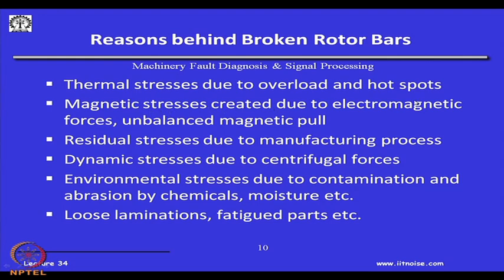Magnetic stresses are created due to electromagnetic forces and unbalanced magnetic pull. I just told you, if the air gap is not maintained, there will be a pulsating magnetic field. During the manufacturing process, all of the bars may not have had the same stress relieving, so some could have residual stress. Because the rotor is rotating, there are centrifugal forces and thus stresses. There could be moisture, abrasion by chemicals, and contamination that could lead to wear and tear of the rotor bar.